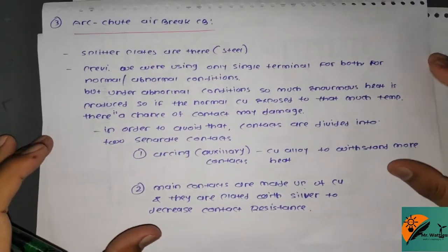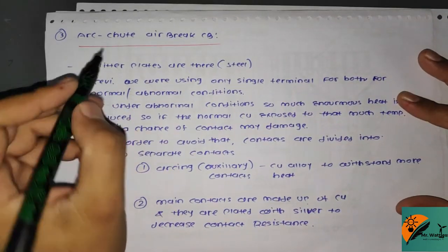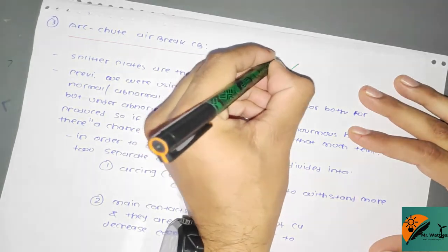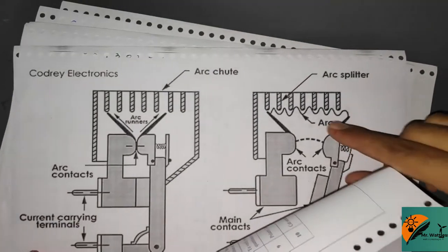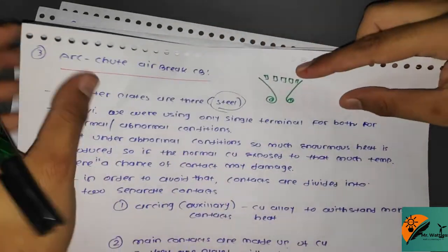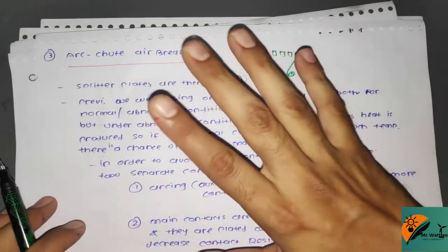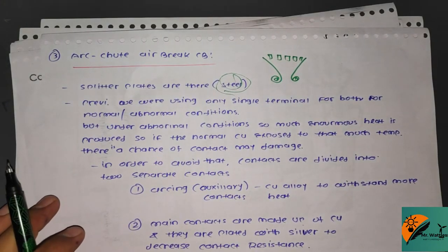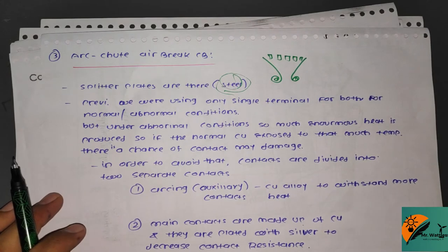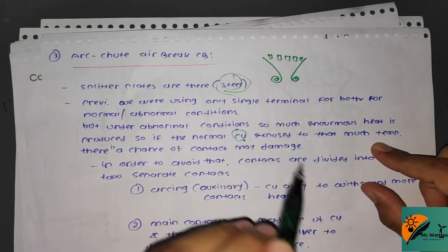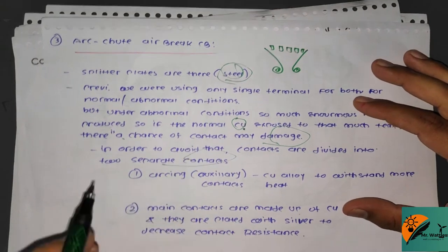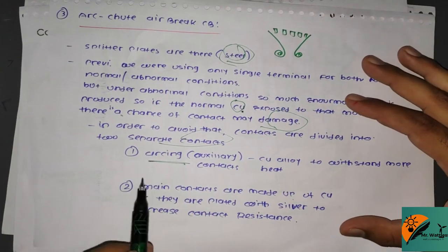Another one is the arc chute circuit breaker. In this type, splitter plates made of steel are present. When the contacts separate, the steel plates act on the arc. Previously, a single terminal was used for both normal and abnormal conditions, but under abnormal conditions an enormous amount of heat is produced. If normal copper contacts are exposed to that temperature, there is a chance the contacts may be damaged.